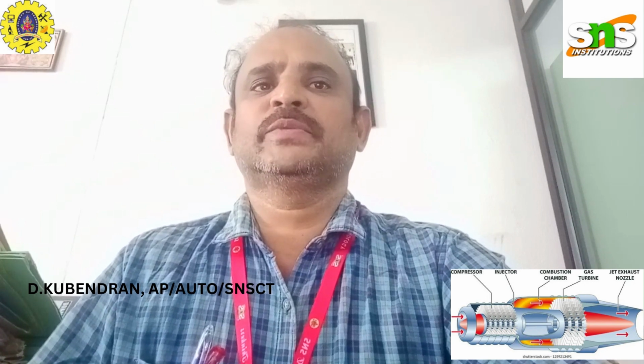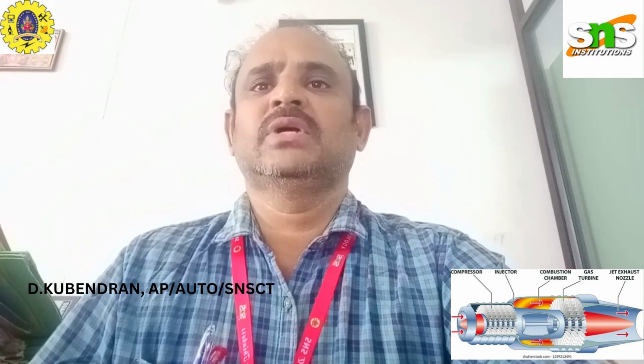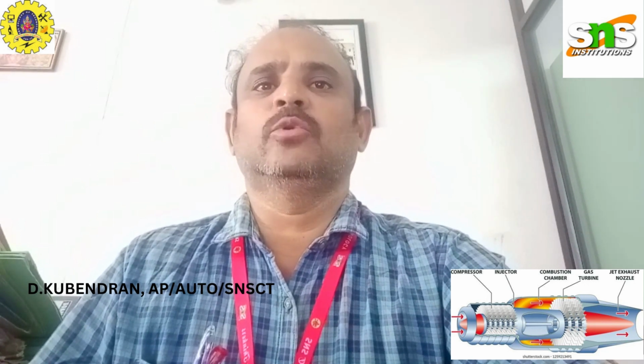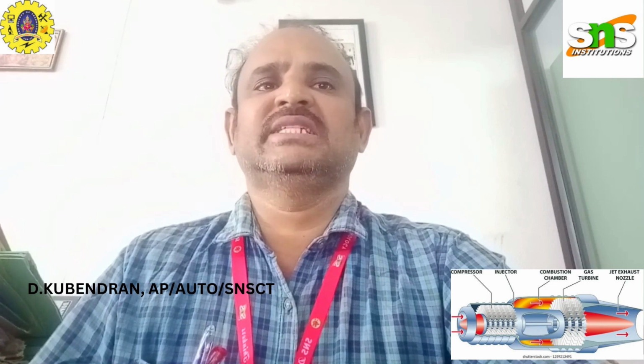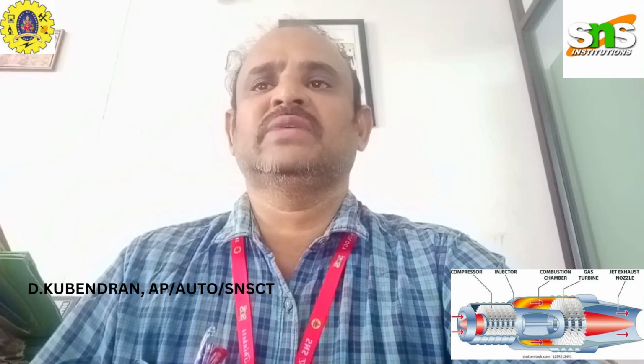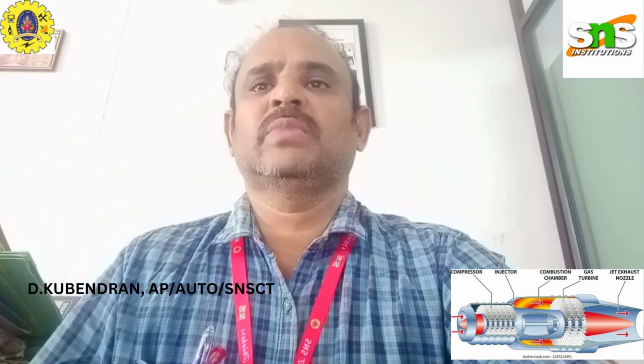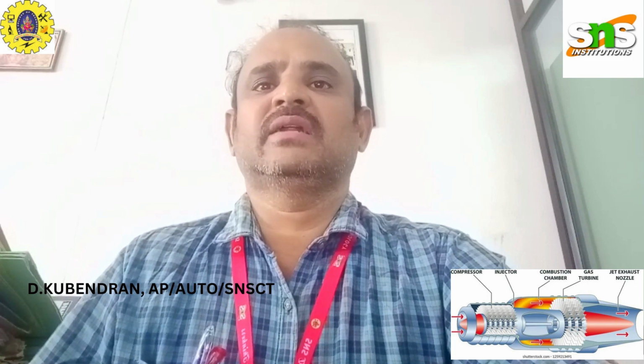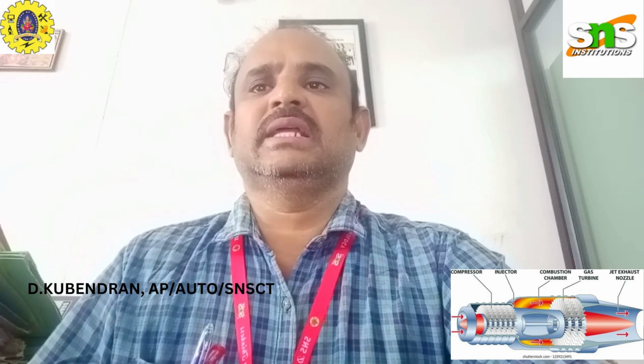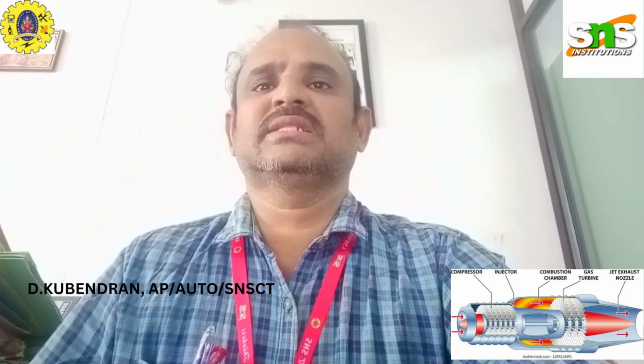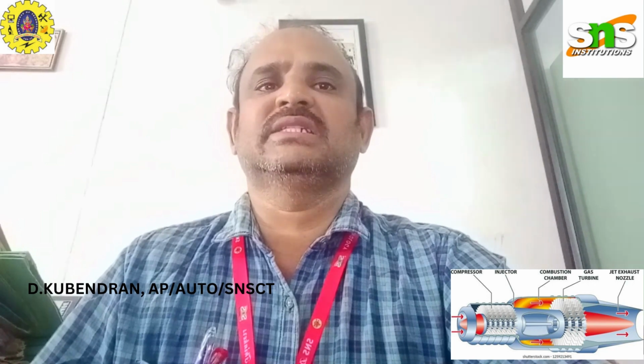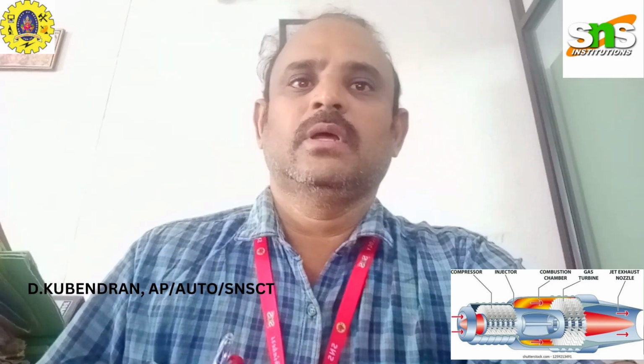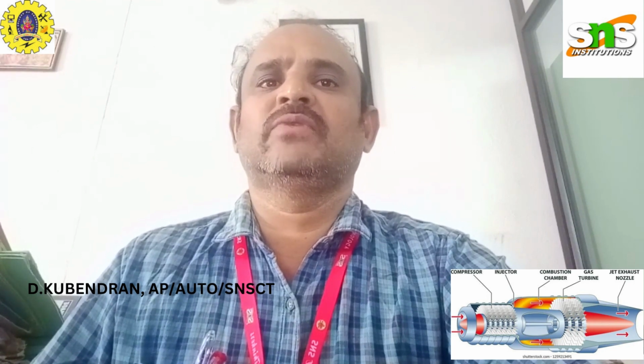In order for tip speed to remain constant, if the diameter of a rotor is reduced by half, the rotational speed must be doubled. For example, large jet engines operate around 10,000 to 25,000 rpm, while micro turbines spin as fast as 500,000 rpm. Mechanically, gas turbines can be considerably less complex than reciprocating engines. Simple turbines might have one main moving part, the compressor shaft and turbine rotor assembly, with other moving parts in the fuel system.